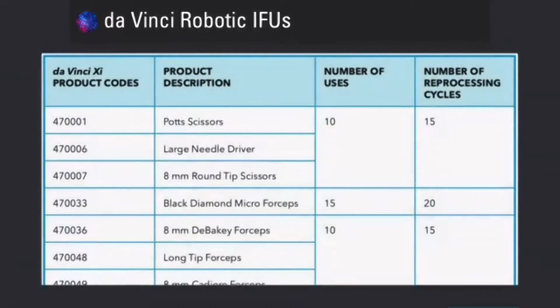Let's look at an IFU document a little bit for the robotic instruments, which are available to you. There at the top is the scissors. It says number of uses 10, number of reprocessing cycles 15. So what does that mean? Well, you could have your instrument in the OR and it won't necessarily be docked. But it does count as a use, even though it hasn't been used. And so it is still in the OR, and it comes down and does need to be reprocessed. You can reprocess it 15 times and you can use it 10 times.